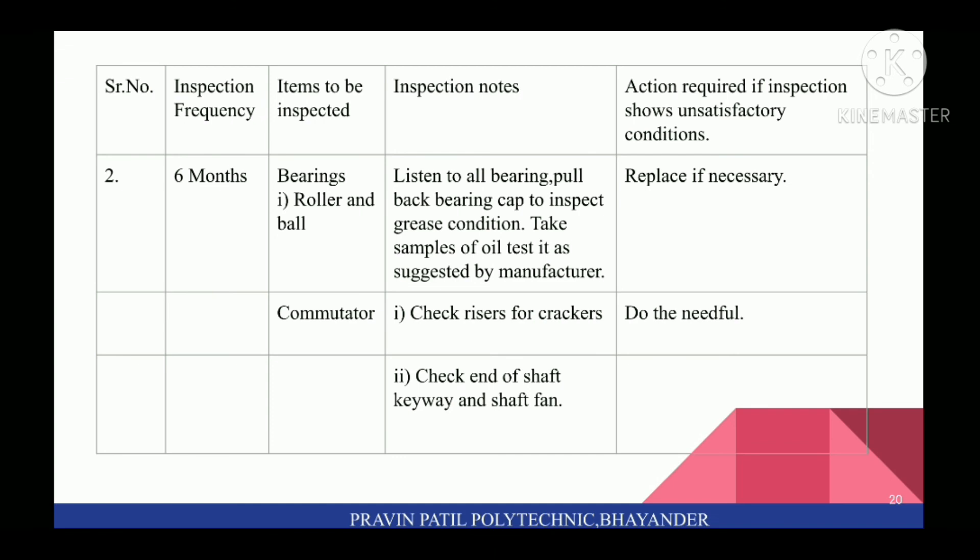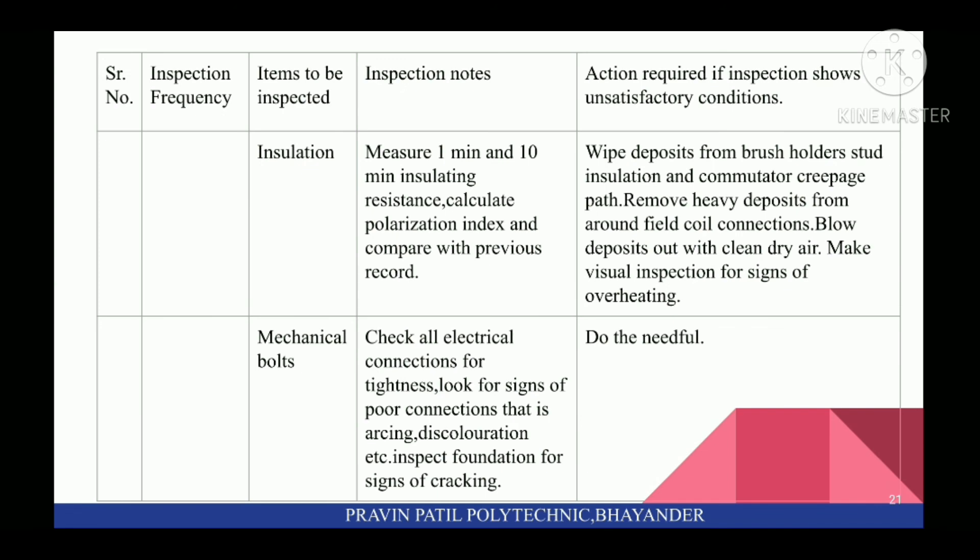Next, check ends of shaft, keyway, and shaft fan. Next, inspect insulation: measure 1-minute and 10-minute insulation resistance. Calculate Polarization Index and compare with previous records. Wipe deposits from brush holder, stud insulation, and commutator creepage path. Remove heavy deposits from around field coil connections. Blow deposits out with clean dry air. Make visual inspection for signs of overheating. Next, inspect mechanical bolts: check all electrical connections for tightness. Look for signs of overheating connections, i.e., arcing, discoloration, etc.